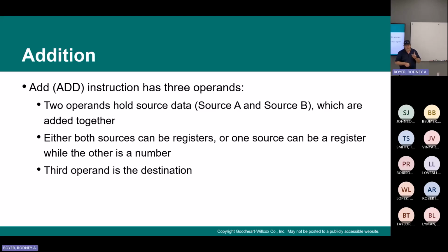If there is no conditional logic, and you say N7:0 add 1, put it back in N7:0, it'll do that every scan. So you're actually counting scans rather than just adding 1.